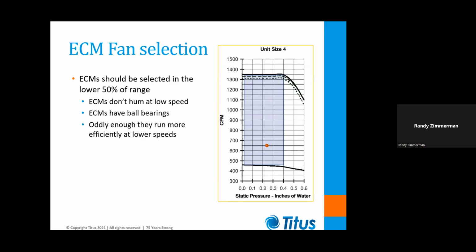Now, ECMs are a totally different game when you're selecting them. They don't burn up at the low end, and actually ECMs have a minimum efficiency of 70 or 80%, depending on who you talk to. But you find that if you turn the speed control down on an ECM, the efficiency actually increases. So it's not hard to get efficiencies up in the 90s, 95, 96% efficiency as you turn the speed down. So I tend to select my ECMs in the lower 50% of their range so that I get a quieter motor and get the highest possible efficiency.